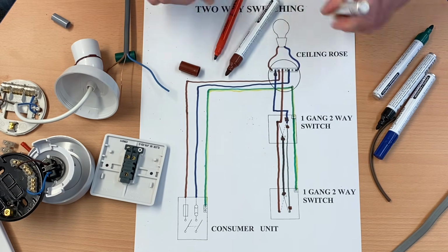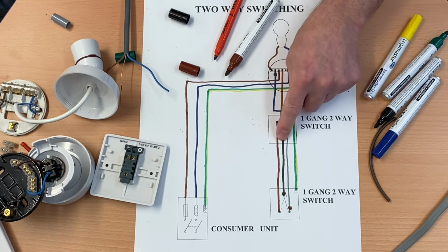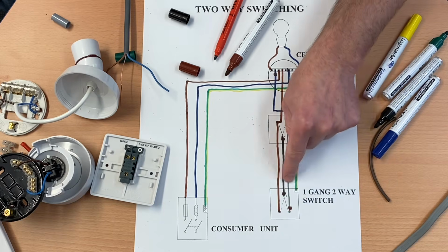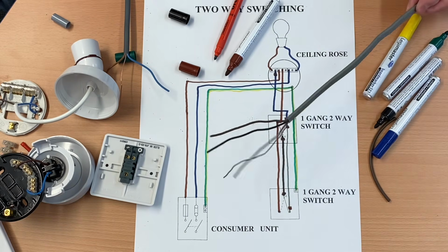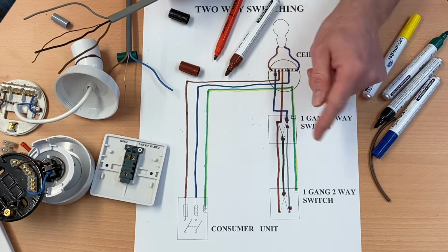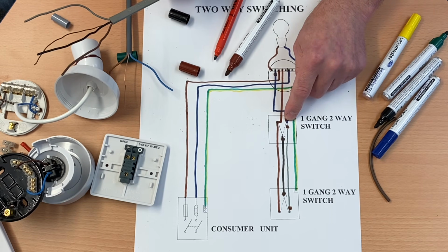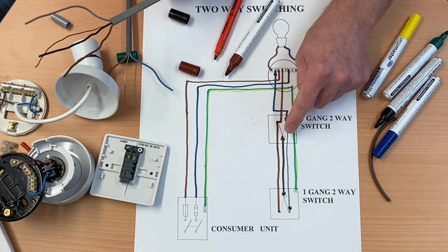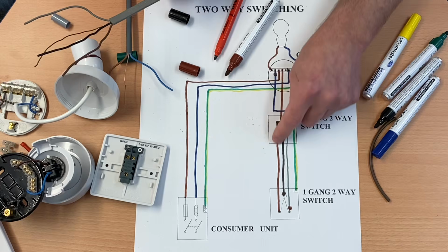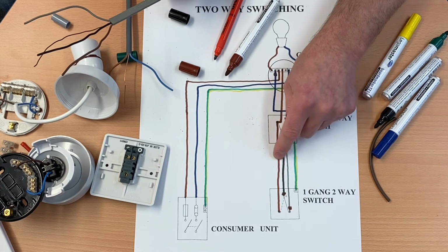So what we've done there is just simply had the original one-way switch maybe, and we've changed that now for a 2-way switch. And this one here is a 2-way switch. And all we've done is introduce one more cable. This cable being a 3 core and CPC. We've put the permanent line, say in L1 or L2, doesn't matter which, the switching line, which we had before in L1 or L2, doesn't matter which, but it's important that we linked our two commons together. We kept that as black, and we had the brown strapper and the grey strapper coming down as well. So these are sometimes called strappers.